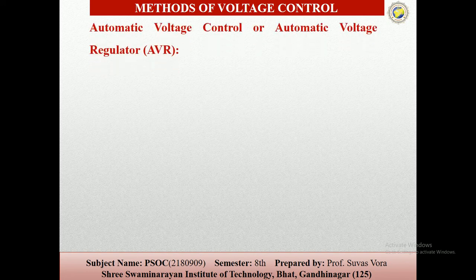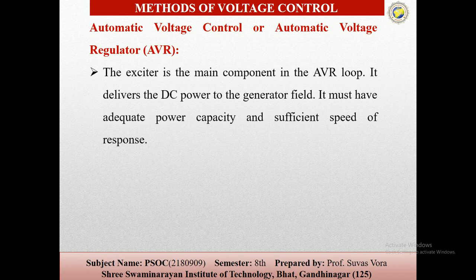Now we study the automatic voltage control, or the automatic voltage regulator. In the automatic voltage regulator, the generated voltage depends on the rotating speed and the excitation current of the generator. So in the AVR system, the voltage is controlled by the excitation current while keeping the speed constant, and this is called the voltage control system or excitation. The exciter is the main component in the AVR loop, and it delivers the DC power to the generator field. It must have adequate power capacity and sufficient speed of response.